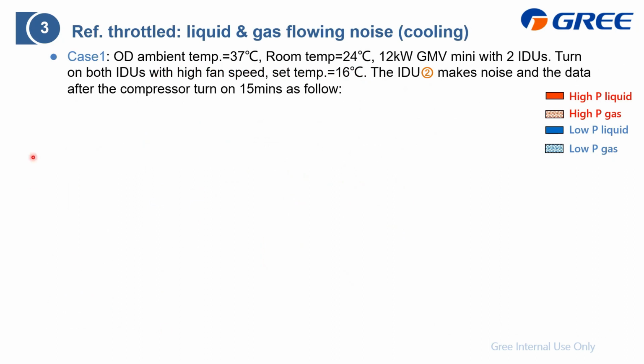And here is a case, and you can find it, verifying this complaint. Our serviceman went to the site and repeated the noise. From the data we recorded, the outdoor ambient is 37, the indoor room is about 24, and it is a 12 kilowatt GMV mini with only 2 indoor units. Our serviceman turned on both of these indoor units with high fan speed. The set temperature is 16 degrees, and we find that after just turning on for 15 minutes, there is some boiling water noise from indoor unit 2, which is this one.